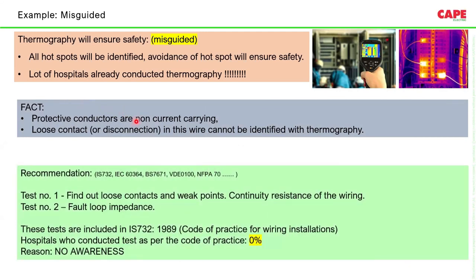Here, the problem with thermography is that loose contacts in the live conductors are found, whereas in the earth conductor or protective conductor, you cannot find out the loose contacts and problems. So IS 732, and also the National Electrical Code 2023, which was launched on 6th of January, has recommended 2 tests which can find out loose contacts in a wiring. Test number 1 is called the continuity resistance of the wiring. You are supposed to measure the continuity resistances. And test number 2 is fault loop impedance. With these 2 tests, loose contacts not only in the phase or neutral conductor, but in the earth conductor also can be found out.